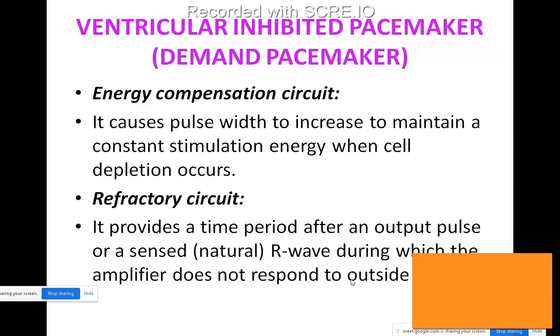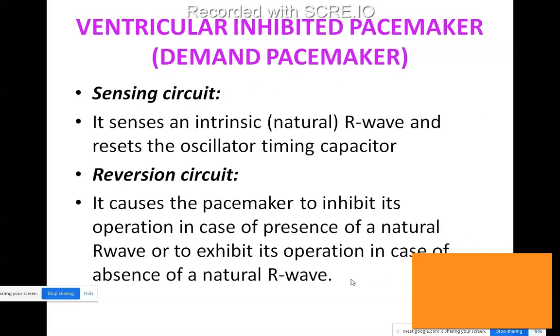And then the refractory circuit. The refractory circuit is nothing but, at a particular time period, the amplifier will not respond to the outside signal. The amplifier will be working only on the R wave signal rather than working with the outside signal. That time period is called the refractory period, and the refractory period maintained by a circuit is said to be a refractory circuit.